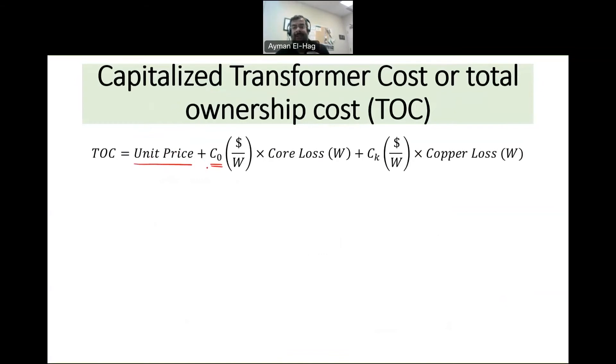Now with this understanding we can answer the question. So this is the capitalized formula, and in some literature we call it total ownership cost or TOC. It equals the unit price - this is the price of the transformer from the manufacturer - plus C₀ which is the factor that we multiply with the core loss, and Cₖ or the factor we multiply by the copper loss.